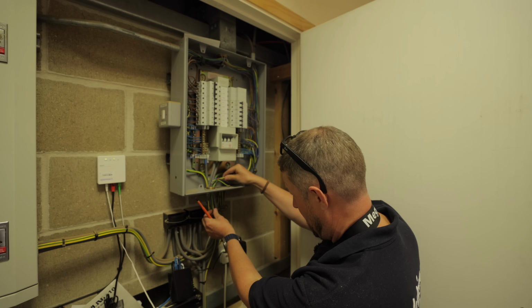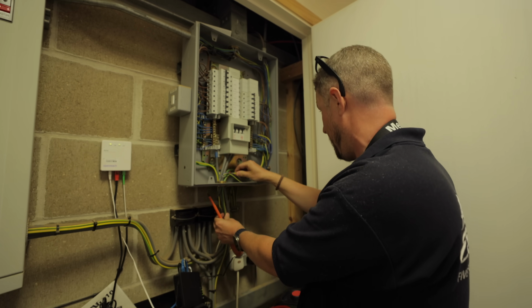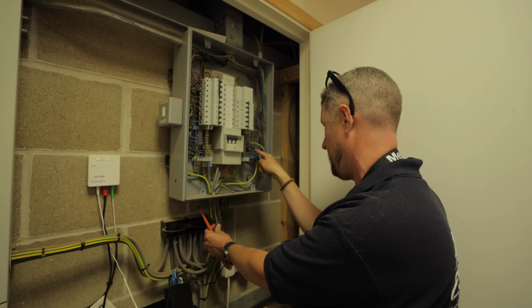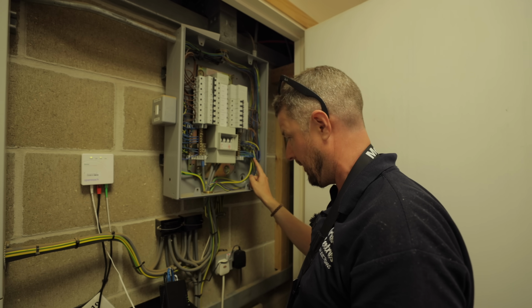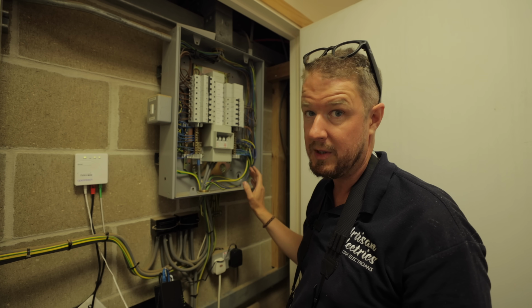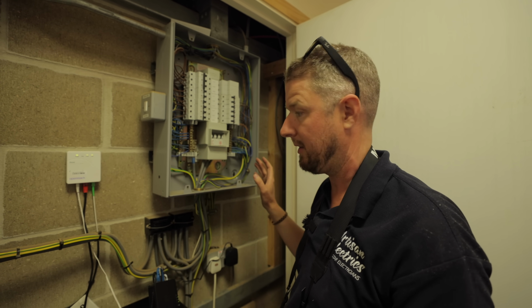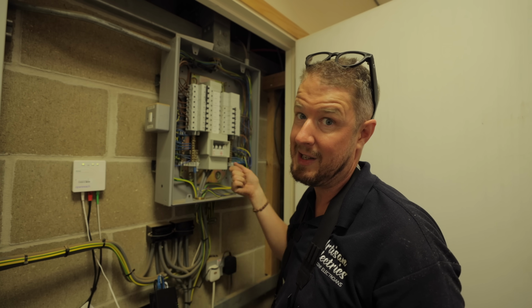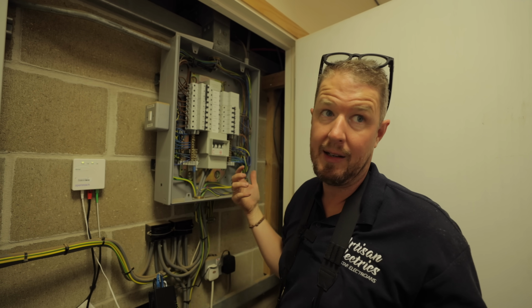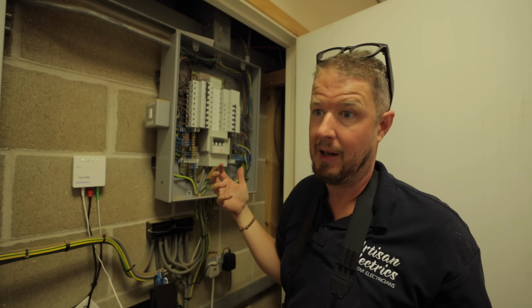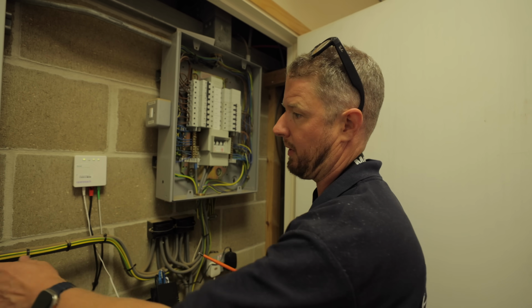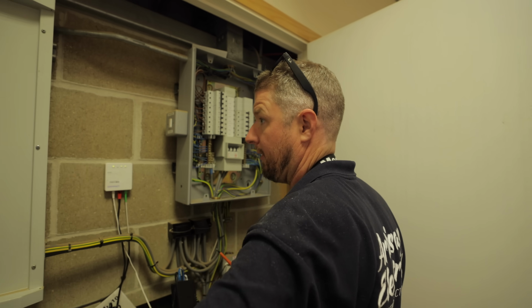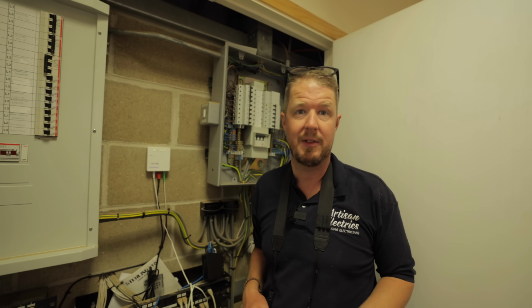For the ZE test, we've got this main earth here, which goes into the main earth terminal there. So for safety, we need to disconnect the main earthing conductor. If we don't turn all the power off and we disconnect the main earthing conductor, suddenly the whole building doesn't have a safety earth connection. So that's quite important. I'm going to do this board first, but I'm going to plunge myself into darkness.